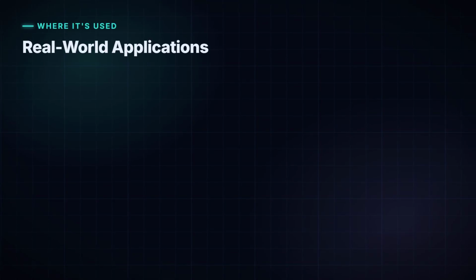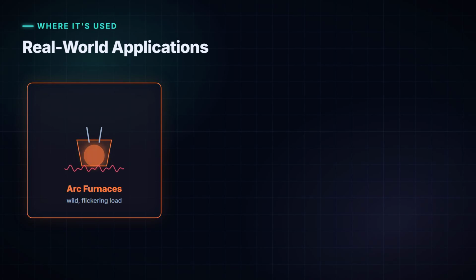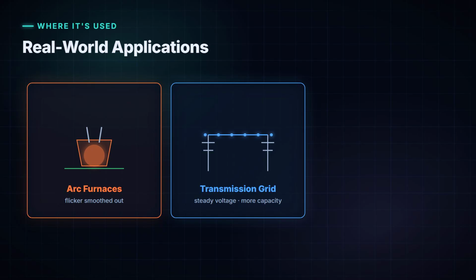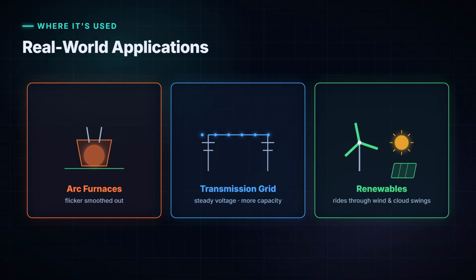So where do we actually find these things? The classic example is the electric arc furnace, used in steelmaking. An arc furnace draws enormous, wildly fluctuating reactive power, and left unchecked, it makes the lights flicker for an entire region. An SVC reacts fast enough to smooth those swings out cycle by cycle. On the transmission system, SVCs are installed at key substations to hold voltage steady over long lines, and to let operators push more power through existing infrastructure safely. And increasingly, you'll find them at wind and solar farms. Renewable generation is variable by nature. The wind gusts, a cloud passes, and the grid connection point needs constant voltage support to ride through those swings. An SVC provides exactly that, which is why it's become a quiet but essential part of integrating clean energy into the grid.